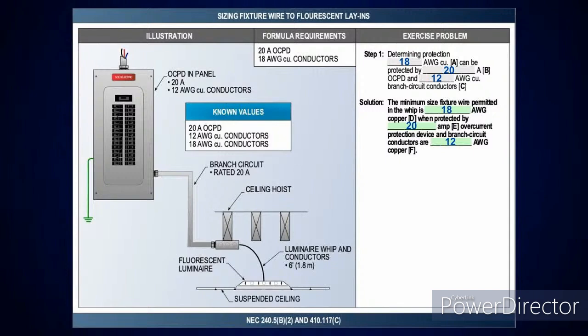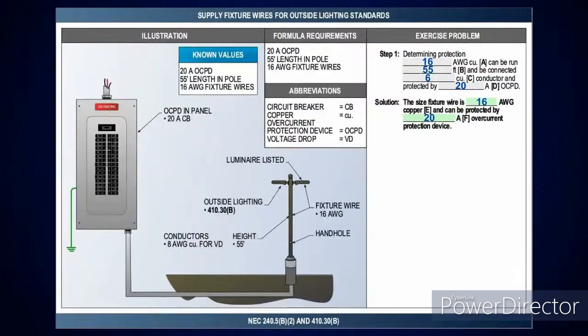Okay? Right. And then your last is where I'm going over to a pole, and this is just like a question, really, but can the number 16 conductors be run 55 foot and be connected to conductors that are protected by a 20 amp overcurrent device? Well, sure they can. And that's where you're going to look at 240.5B2 for the length of the conductors, and 410.30B is where we're looking going over feeding this outside lighting.